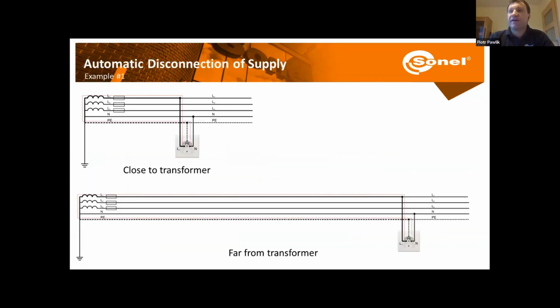Okay, so now let's look at a few examples. We are going to measure fault loop impedance. Here we are in a TN system. First example, we are closer to the transformer. Second one is we are further away from the transformer. So the question is where the value of fault loop impedance will be lower. Okay, a little time to think about it. And now the answer is that the lower value we are going to have closer to a transformer.